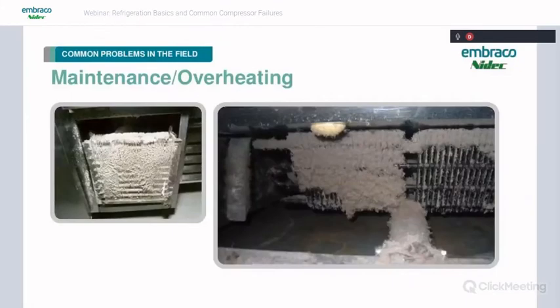And then, of course, there's maintenance. We see a lot of this, just plain a lack of maintenance, either by not knowing or people don't want to call for service. They don't want to pay the service technician to come out and maintain the system. Obviously, especially in a commercial environment, you're going to see this type of buildup on the condenser coil. And then your system can't reject the heat anymore. So it's just going to sit there and heat soak.